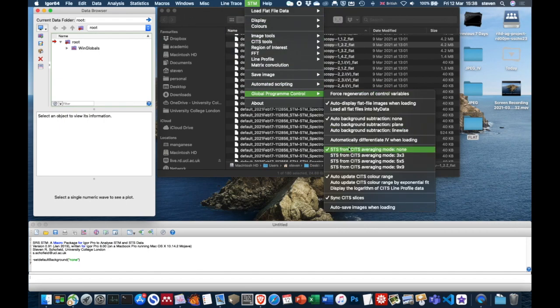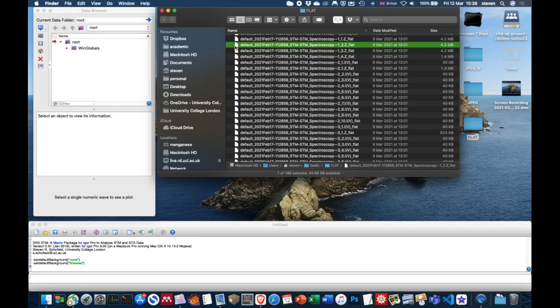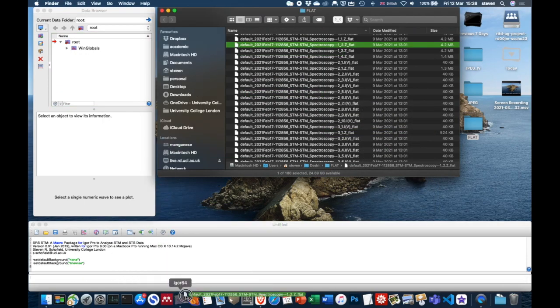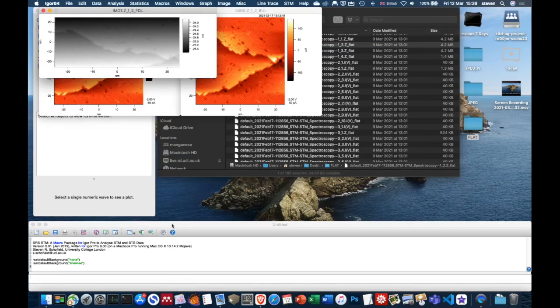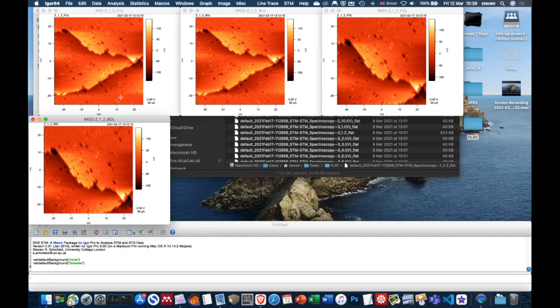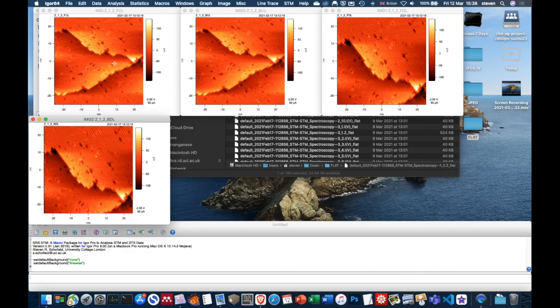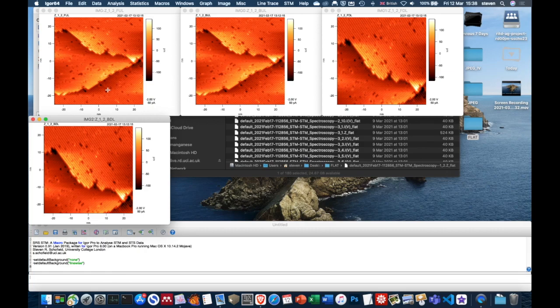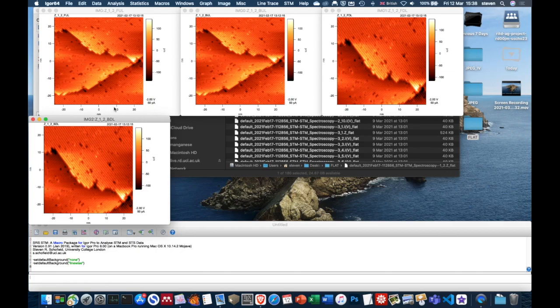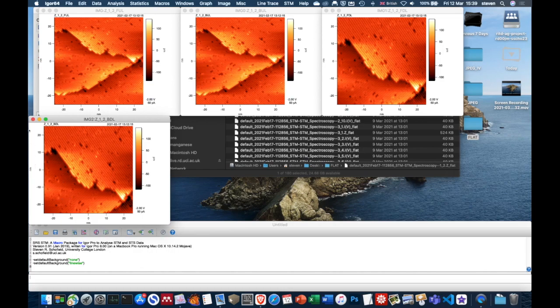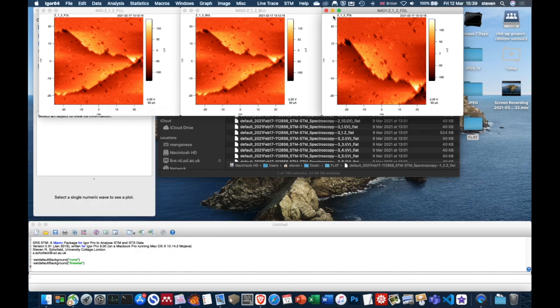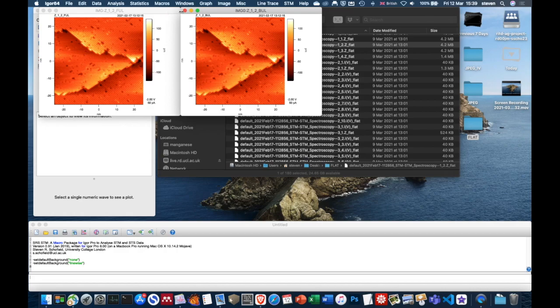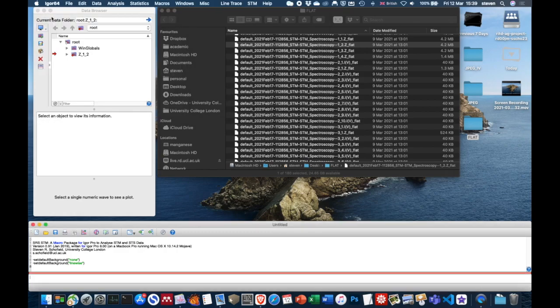Conversely, we could also have set that to global program control, auto background subtraction. If we make that line wise, then it will do a line wise subtraction on your data. And the thing about line wise subtraction is that it now introduces artifacts into the image. You can see that this little corner of the terrace looks like it's higher than the rest of the terrace. And that's just because what the program is doing with line wise subtraction is it's removing the background from each horizontal line as it goes. So the height information in the Z direction is now no longer really valid anymore. So it introduces artifacts into your data. But on the other hand, if you have data that has a lot of curvature to it, then sometimes it's nice just to run the line wise. You have a better chance of actually seeing the information in the image if you run the line wise subtraction. But when you're doing the detailed analysis, you're much better using a plain subtraction.